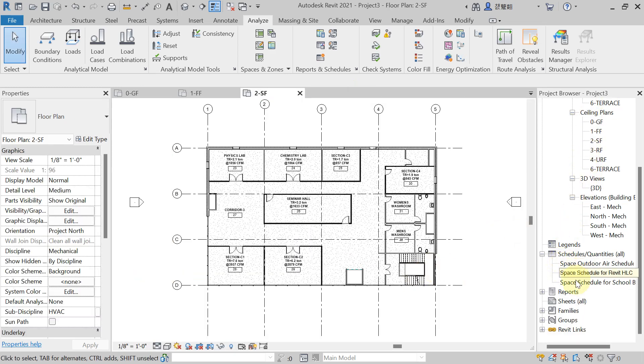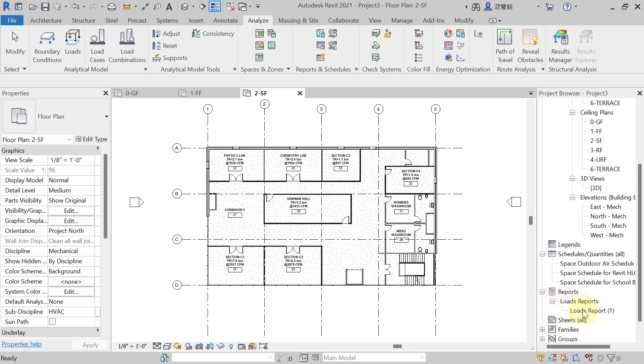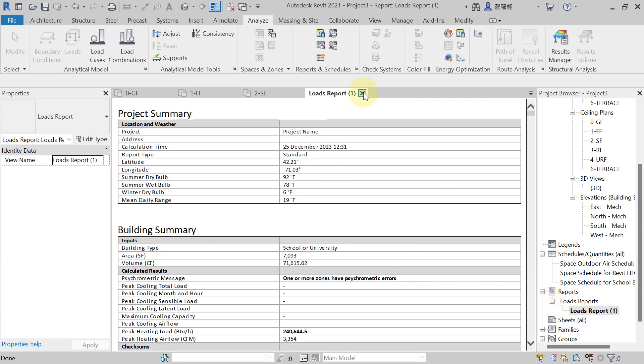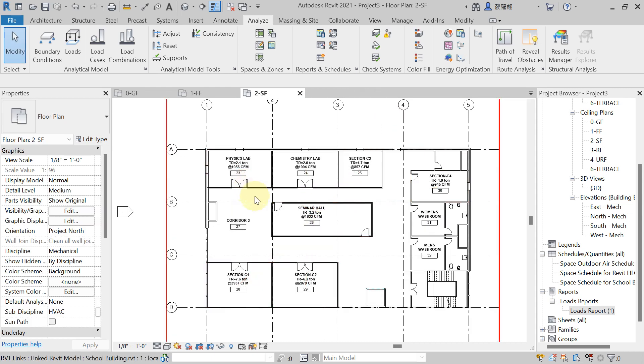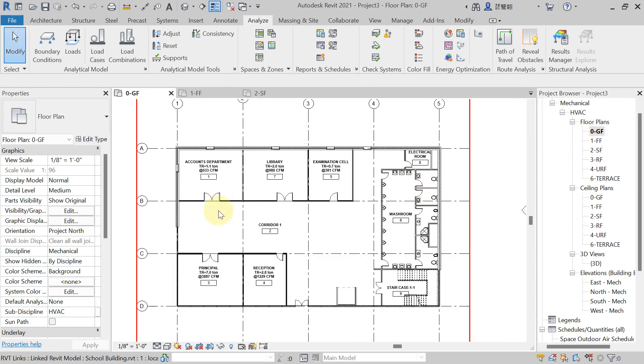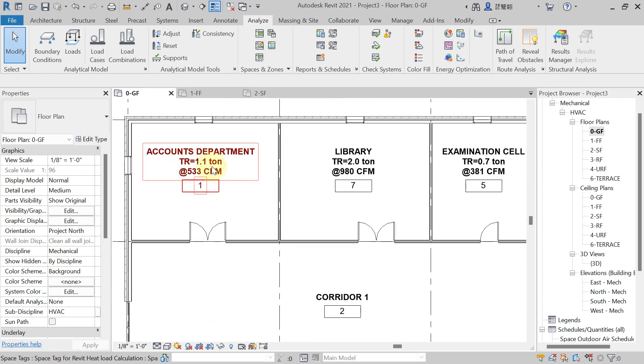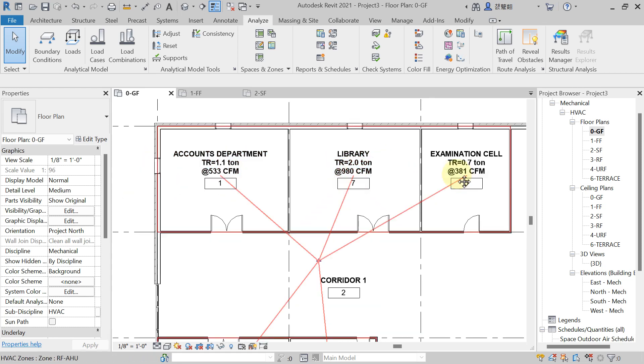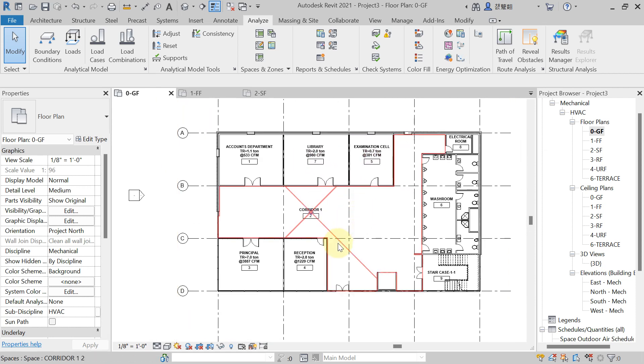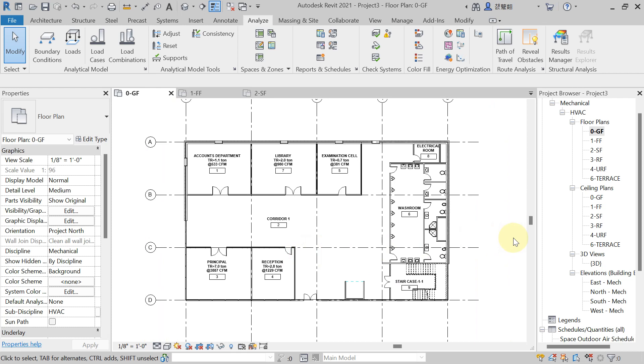Close the load report. The report is automatically saved in the Project Browser under Reports — hit the plus sign to reopen it anytime. After the heat load calculation, go to the floor plan (e.g., Ground Floor). In the tagging view, you can see the TR (Ton of Refrigeration) cooling load value and the supply CFM value displayed for each space. That is how we do heat load calculation in Revit.